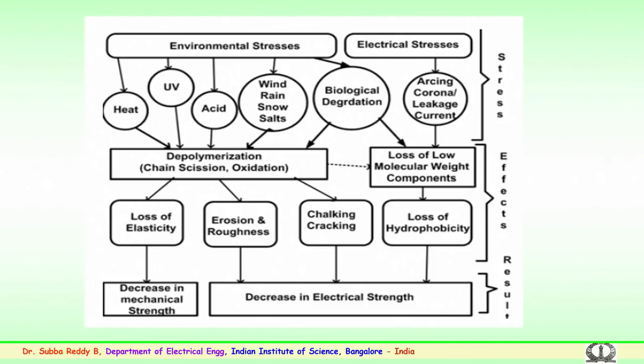It could be of various temperatures that the insulators have to perform in. Ultraviolet, again as mentioned, could be ultraviolet radiation from the sun. In case of very high temperature, the sun's radiation could make the insulator surface brittle over a period of time. Or the ultraviolet radiation could be generated because of improper design or placement of the corona control rings, or because over a period of time, due to wind or mechanical issues, the corona control rings have shifted. The surface of the corona control ring could then create a continuous corona, where UV from the corona could also be generated and degrade the surface.